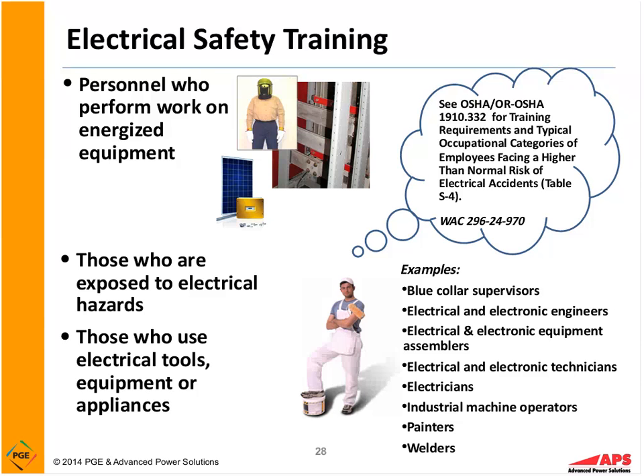use, okay? How about those other folks that are not doing electrical work, but they're exposed, they're working in the area, and they see the cabinet door open? Do they know to stay out of there? Do they know what that danger tape means? Okay, if you have, let's say, someone doing janitorial work or outside work, let's say cutting a hedge with an electric hedge clipper, do they know about the equipment grounding conductor requirements? Do they know to use ground fault circuit interrupters? So it's not just those doing electrical work.